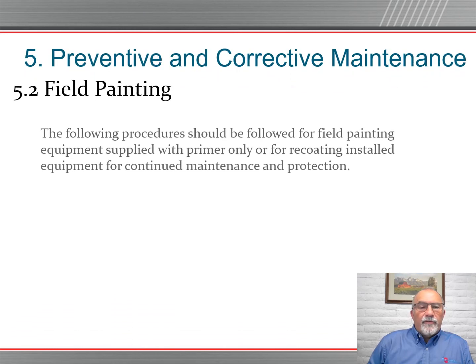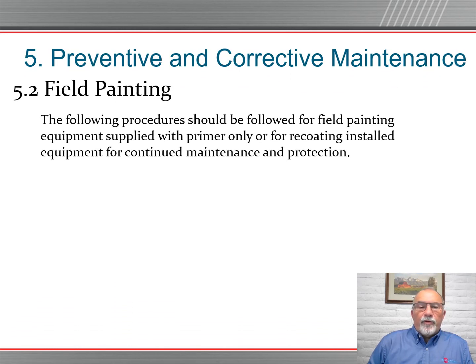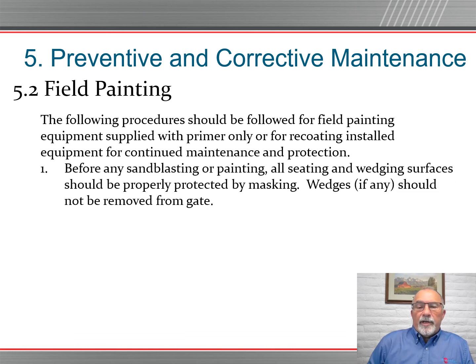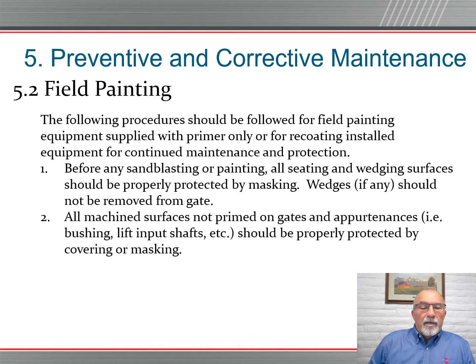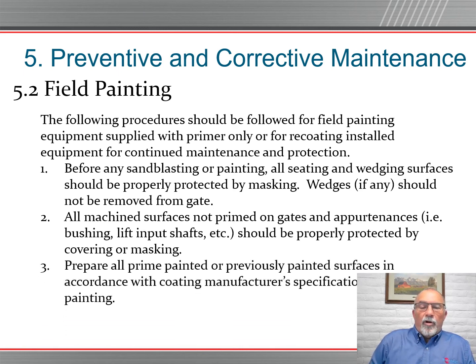Preventative and corrective maintenance. Field painting. The following procedures should be followed for field painting, for equipment supplied with primer only or for recoating installed equipment for continued maintenance and protection. Before any sandblasting or painting, all seating and wedging surfaces should be properly protected by masking. Wedges, if any, should not be removed from gate. All machine surfaces not primed on gates and attachments should be properly protected by covering or masking. Prepare all primed, painted, or previously painted surfaces in accordance with the coating manufacturer's specification prior to painting.